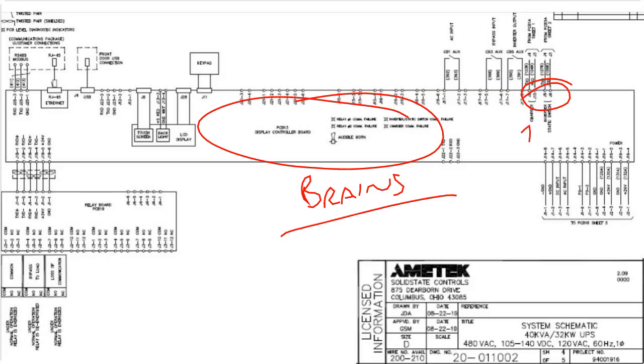This goes to the charger board and this goes to the inverter static switch board, okay? And we have our relay board connected to that system as well. So that is all the boards in the system. We mentioned the charger and the inverter static switchboard earlier, and now PCB 13, that is the brains of the system.